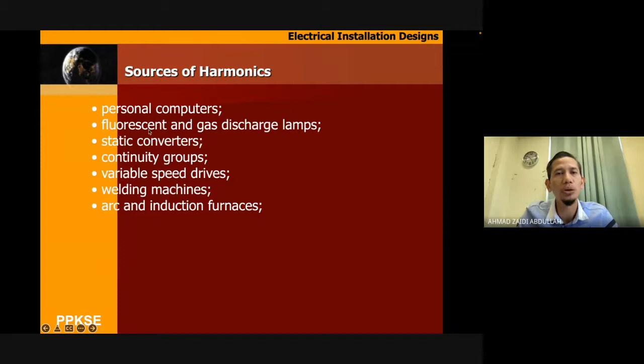So this input you can also use for your report, actually, under justification. For those who have not submitted the report yet, there is still time to edit. Because fluorescent lamp has what we call the ballast. That ballast will produce harmonic, and that harmonic will affect the power system. If you can discuss that, you can get a good mark on your assignment 1, because you need to justify why you choose that model of lamp. Maybe you choose LED? So you can discuss how fluorescent has harmonic compared to the LED with very little harmonic, and so on.